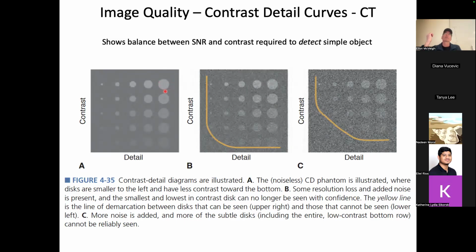Contrast is a molecule that absorbs X-rays. And so you can create a brighter picture by putting in a lot of contrast, or you can dilute the contrast to 50% and make less contrast. But we're going to create a phantom that has these vials in it. They'll be filled with contrast. Those are background. Let's say that's plastic, and it has a certain CT number. This has a certain CT number based on the amount of contrast that's in this vial. And then as I reduce the concentration of contrast, the difference between the background and that signal goes away.